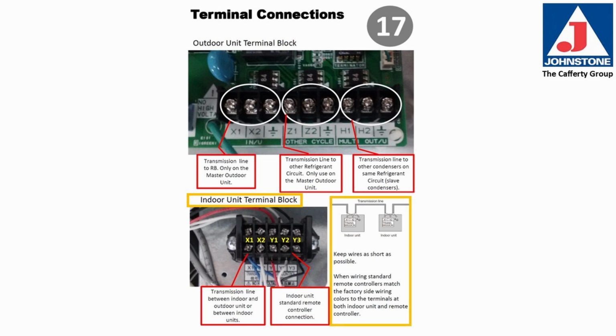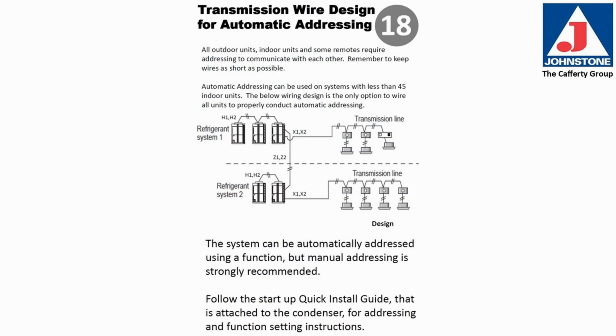Keep the wires as short as possible. When wiring standard remote controllers, match the factory side wiring colors to the terminals at both the indoor unit and remote controller. The transmission line wire connections for automatic addressing. All outdoor units, indoor units, and remote controls require addressing to communicate with each other. Remember, keep the wires as short as possible.